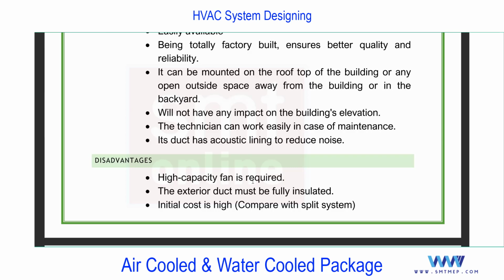In ductable split, outdoor is outside and the duct is going to start from the AHU, and AHU we can place inside the building. So the length of the duct means starting from inside the building only. So, if the length of the duct decreases, the fan capacity, the static pressure which is used to supply the air, also decreases, meaning the HP of the fan motor will decrease. But in case of package, since we are placing away from the conditioned space, or if you talk about air cooled package, we are placing it outside the building. From that point to supply the air to the air terminal, we require higher capacity, and that will increase the air side running cost.